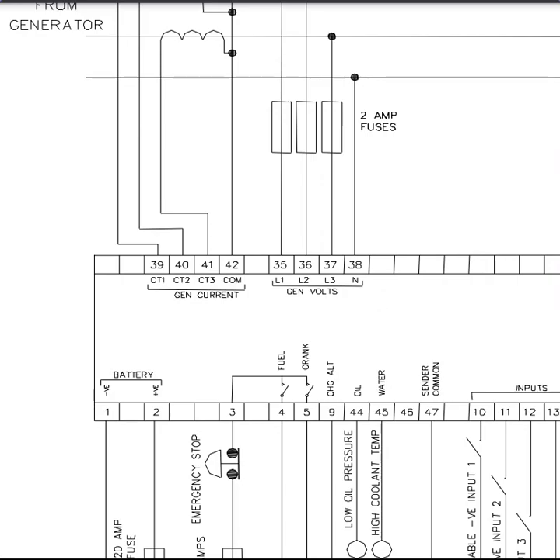You've got to get experience hooking up like 6 phases per leg. And you've got to invest in the right tools. Make sure you've got good meters. Get a Fluke, a good amp clamp, a good resistive meter that can measure like 0.001 or 0.0001 ohms. Having the right tools is just as important as having the experience. If you have the experience but not the tools, you can't do the job. And vice versa, if you've got the tools but not the experience, you don't know how to do the job. Bottom line.